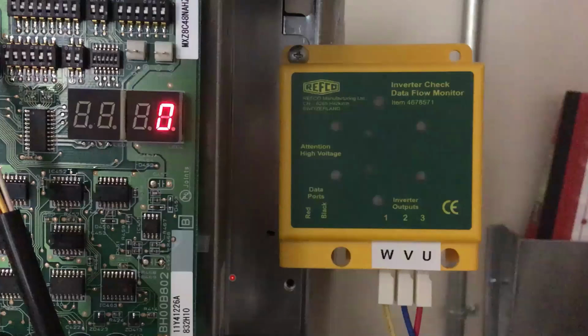I'm going to show you a little video here of the inverter in action. This is on a smart multi-unit in our training center. I connected this Refco inverter checker to the output of the board. And you're going to see this inverter perform two basic functions other than running the compressor, which it will do at the end. The very first function that it's going to perform is to look for a short to ground. This is going to happen real fast. You have to be watching the screen. You're going to see 3 of those lights blink on and off extremely fast. That's the inverter looking for a short to ground.